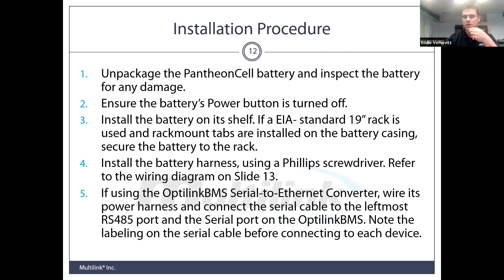Step 5: if you're using an Optilink BMS serial to Ethernet converter, wire its power harness and connect the serial cable to the leftmost RS-485 port on the Optilink BMS. The serial cable has two labels on each opposing end, so make sure you're installing it to the appropriate port.